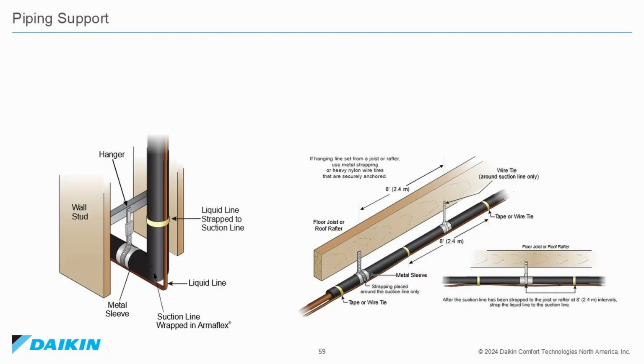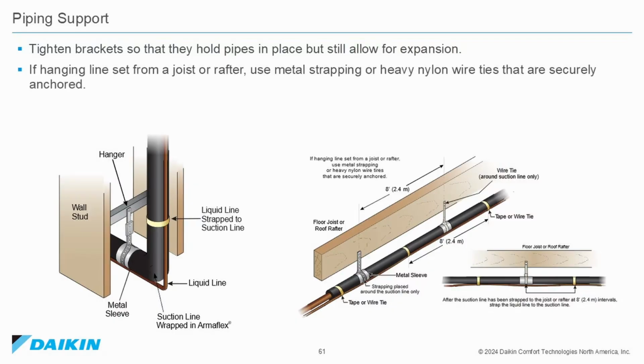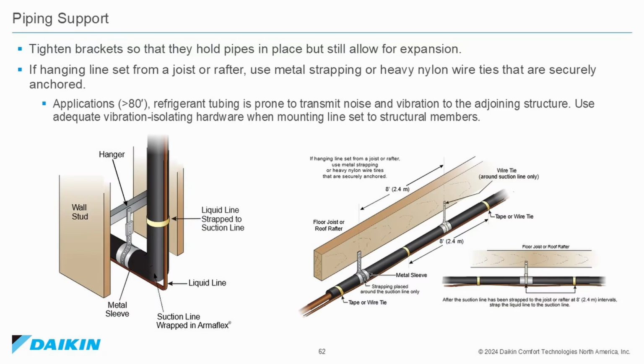Piping support. Tighten brackets so that they hold the pipes in place but still allow for expansion. If hanging the line set from a joist or rafter, use metal strapping or heavy nylon wire ties that are securely anchored. Applications with greater than 80 feet of refrigerant tubing are prone to transmit noise and vibration to the adjoining structure. Use adequate vibration insulating hardware when mounting the line set to the structure.